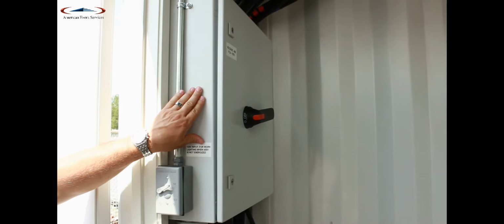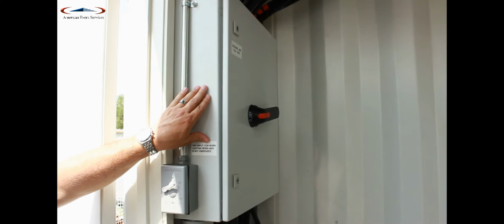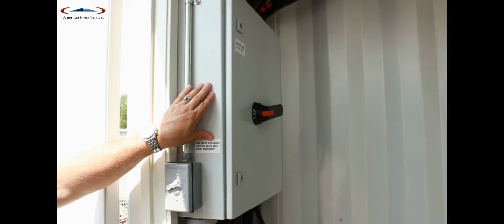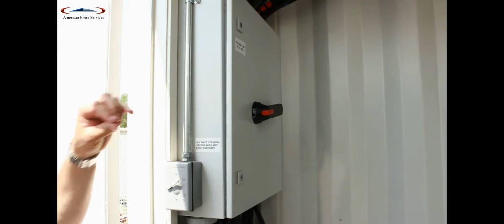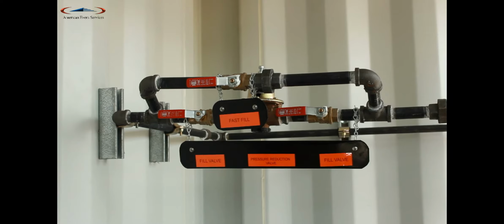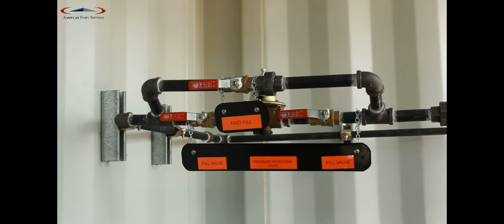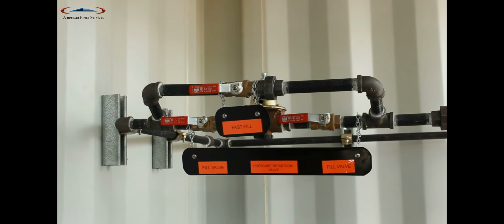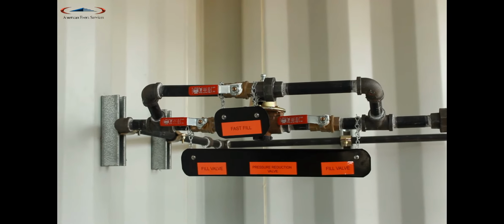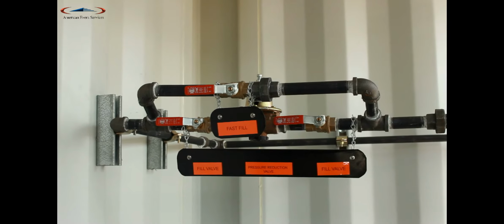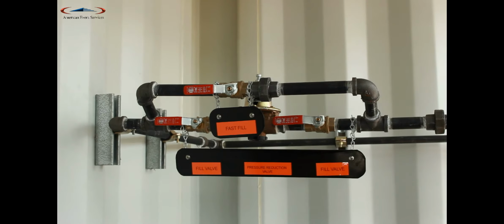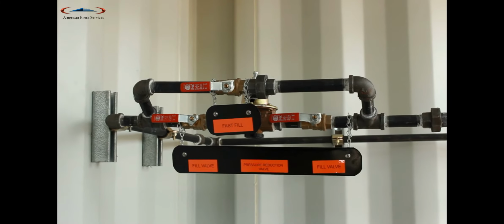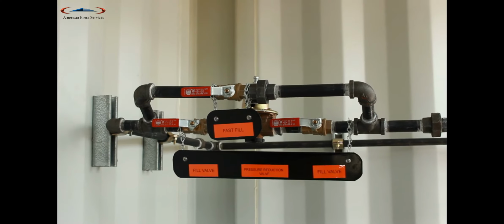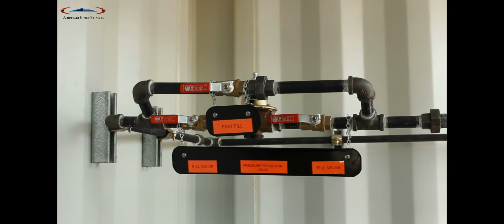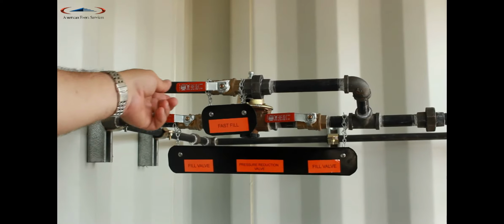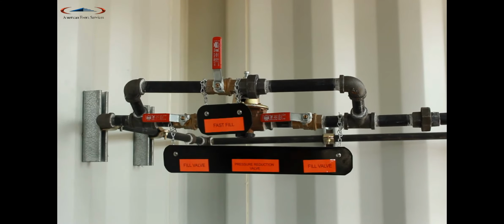This is our 1600 amp disconnect for the entire unit. It is an adjustable breaker that's set optimally for this configuration. We have fill valves along with a pressure reduction valve. The pressure reduction valve is plumbed in to keep the pressures in the boiler at a minimum of 12 psi. When you're filling the system, you can also bypass that reducing valve to fast fill. But when you're operating, you've got to make certain that that bypass is closed and the reduction valve can do its job.